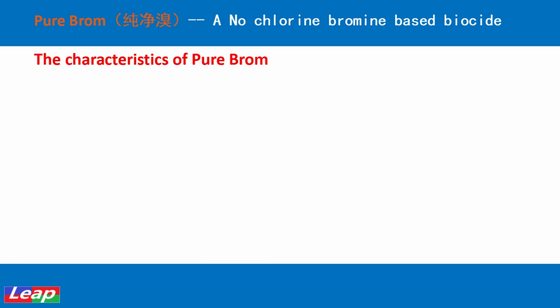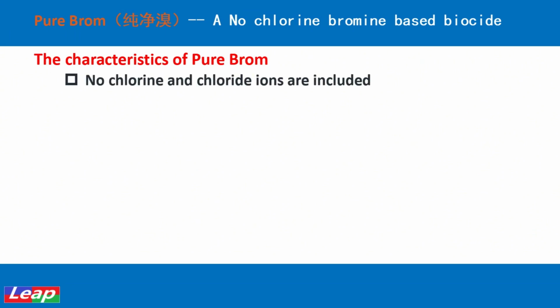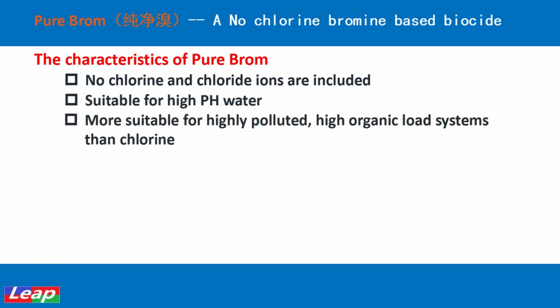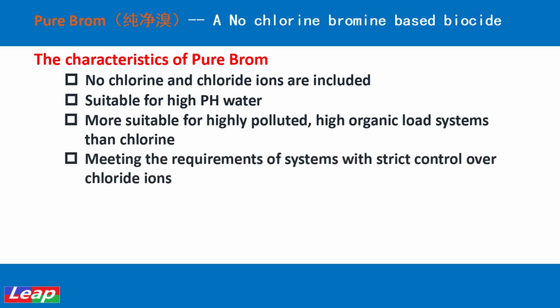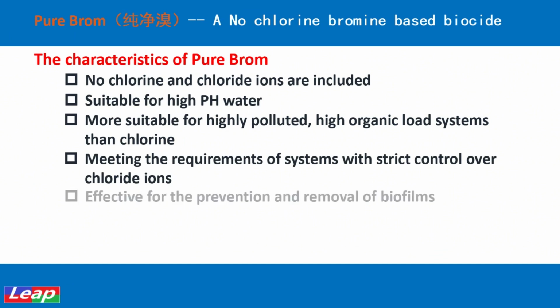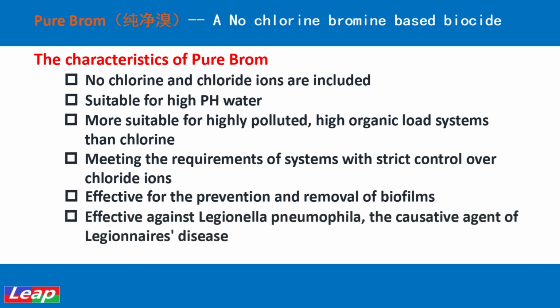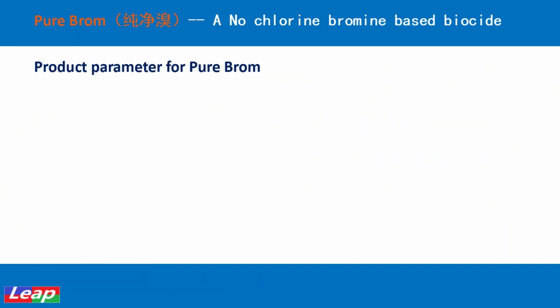Our summary of the advantages of Pure Brom is as follows. No chlorine and chloride ions are included. Suitable for high pH water. More suitable for highly polluted, high organic load systems than chlorine. Meeting the requirements of systems with strict control over chloride ions. Effective for the prevention and removal of biofilms. Effective against Legionella pneumophila, the causative agent of Legionnaires disease. High stability. This is the parameter of Pure Brom.